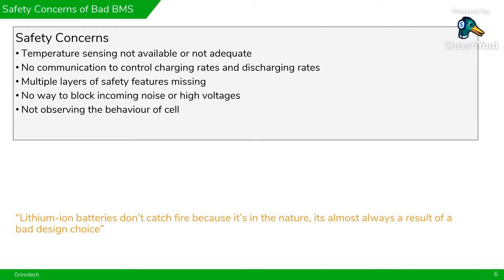That's also a safety risk, because if there is over voltage or under voltage, the BMS will simply cut off instead of requesting the charger or the vehicle to stop discharging or charging. Imagine you're driving on the highway at 60 kilometers per hour and suddenly the battery cuts off. You lose power, you cannot do anything, and you cannot immediately stop because vehicles running behind you will run into you. So it becomes very tricky and a big safety risk. That's why sudden cut off is not recommended.